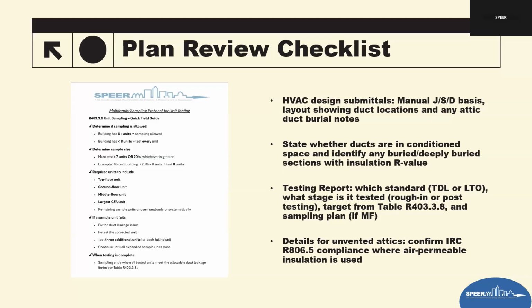And then testing report requirements. Reviewers should verify that the builder and/or third party is specifying the testing standards. Sometimes they don't list it. They just show a CFM that it's actually tested at. But it should be total duct leakage, not leakage to outside, since the IECC no longer allows leakage to outside in most compliance paths. The plan should also indicate when the test has occurred, whether it's rough-in or post-construction.